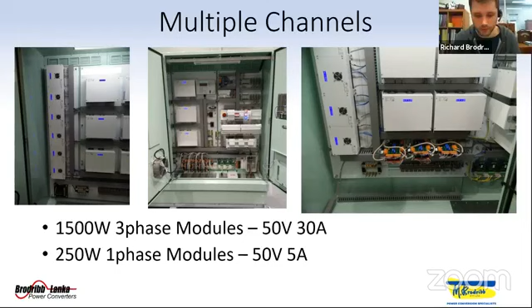Each module has its own isolated output, but this system called for a common negative. Additional sub-circuits of each switch mode CP rectifier were also required. This made for a total of 98 sub-circuits with individual current monitoring. The individual installation electricians inspected the equipment and were able to provide some additional information on the anode cabling. As such, the terminals were changed to bridge terminals, allowing for terminations of the other cores. This saved the client and electricians time and money on site from having to do rework, thus allowing for easier and quicker installation on site.